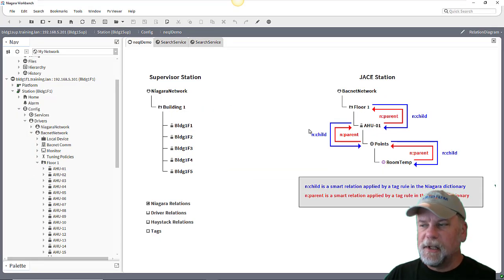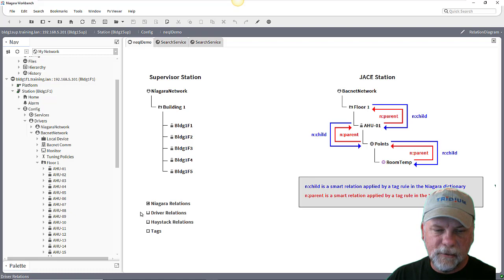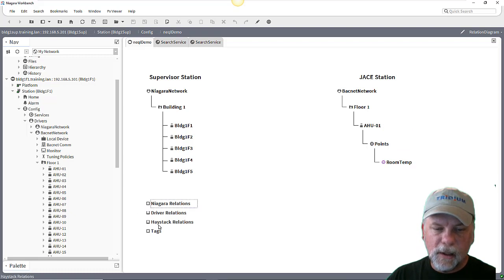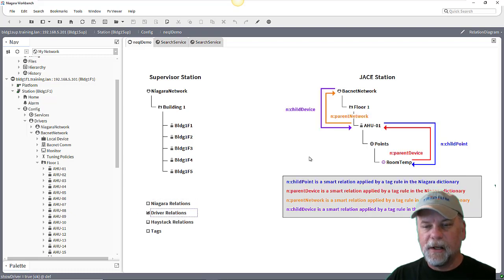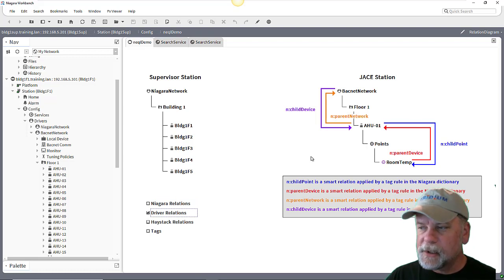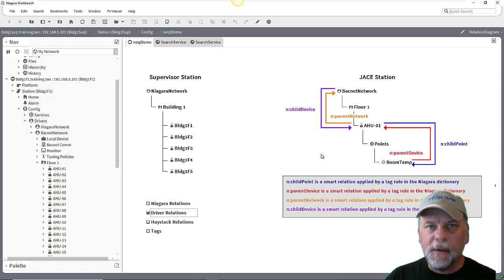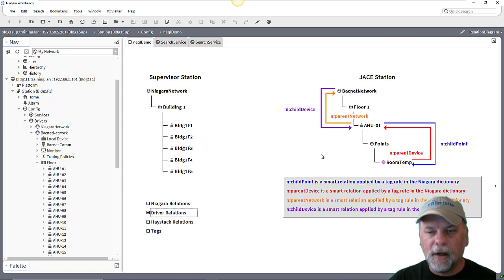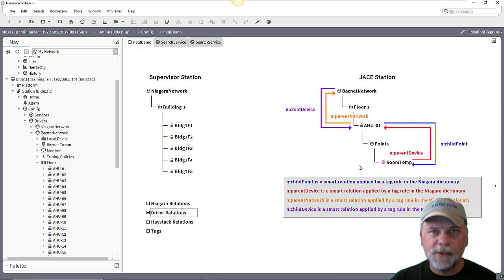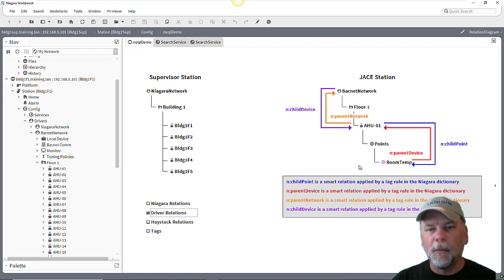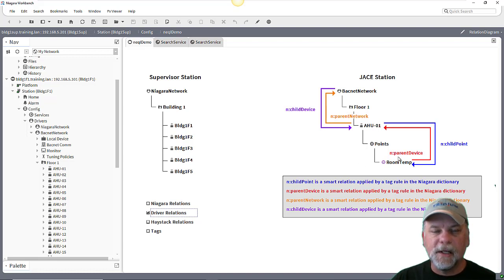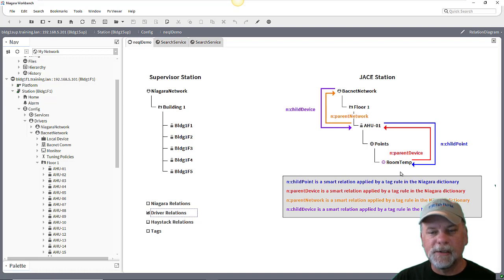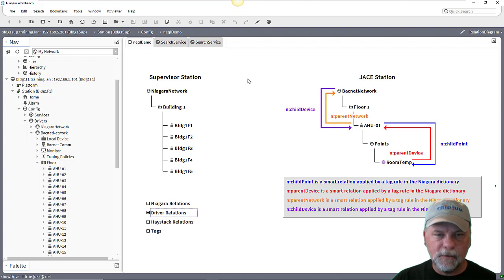So that's using just the Niagara dictionary, the smart relations that are available there. Now there's also the Niagara dictionary has these driver centric relationships as well. So maybe if I wanted to be a little more fault tolerant of the fact that my points might be in different point containers underneath the points folder and they might be a different number of levels deep underneath the points container, I might want to consider using say a parent device relation outbound or an inbound child point, because regardless of the number of levels between the point and the device this should resolve correctly.